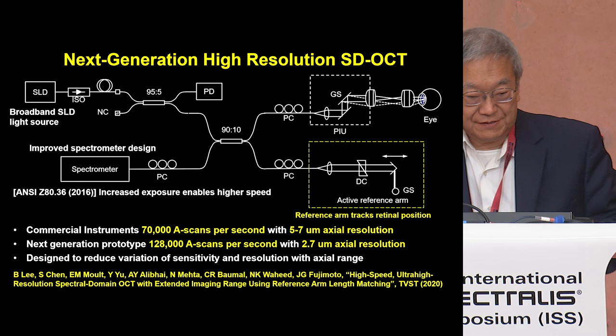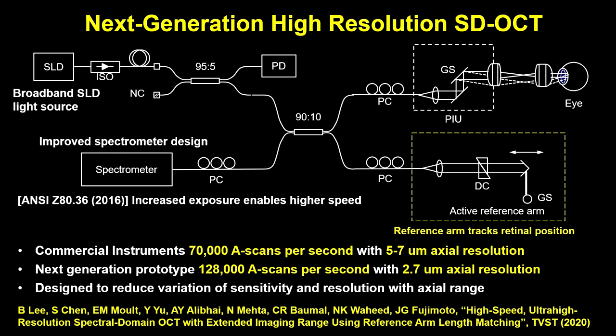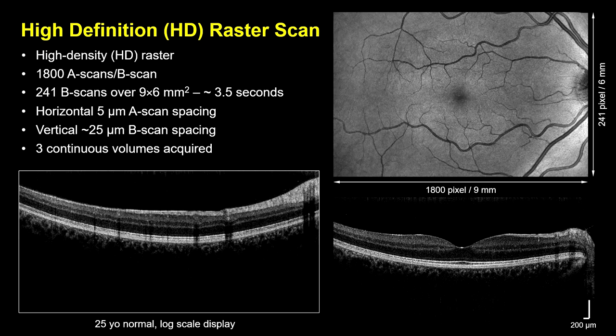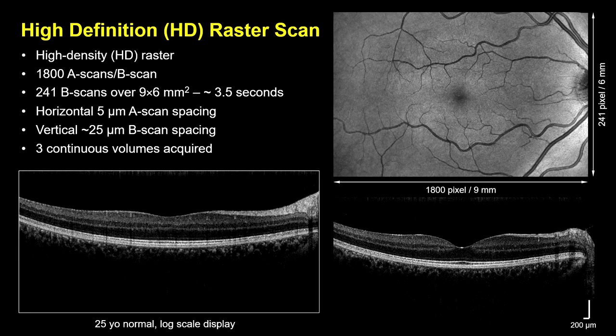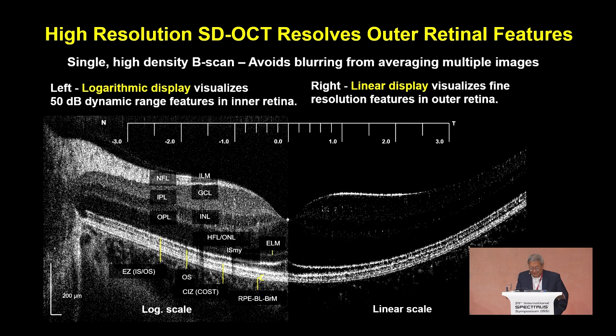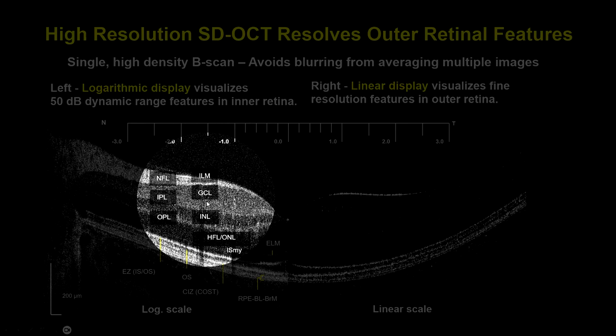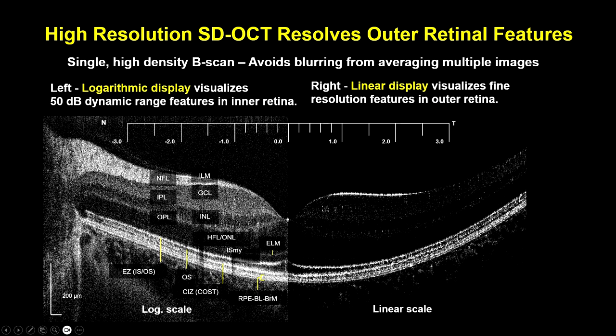This shows an example of a prototype instrument. The specifications are essentially the same as the Heidelberg high-resolution instrument: less than 3 micron axial resolution, 128,000 axial scans per second. With this type of speed and resolution, it's possible to do high-definition scanning covering a 6 by 9 area of the macula. By displaying these images using different scales — the conventional log scale versus a linear scale — the linear scale trades off dynamic range but allows us to see features in the outer retina which would not normally be resolved with standard resolution.